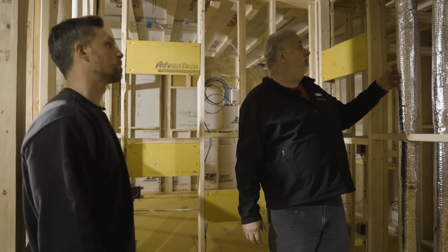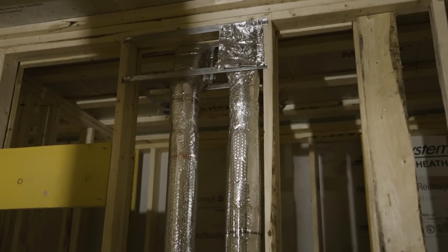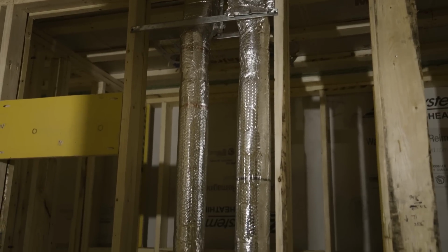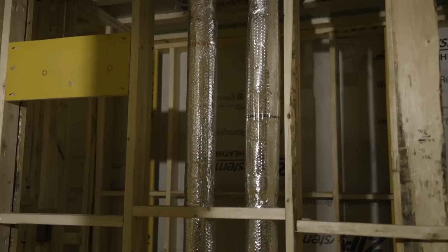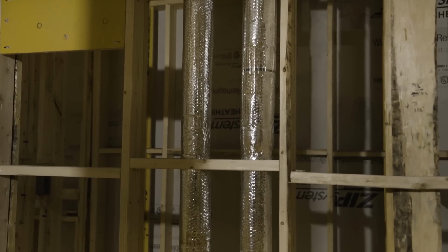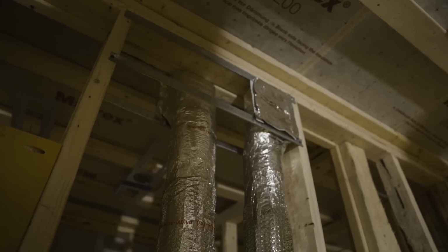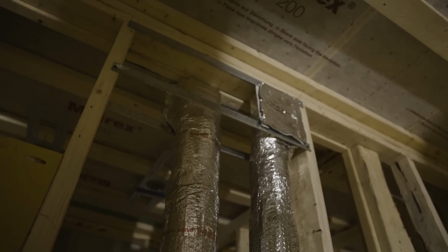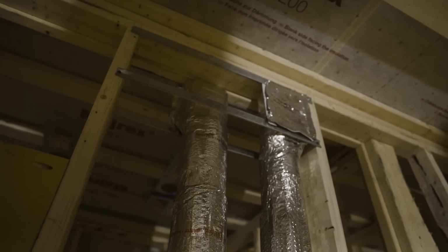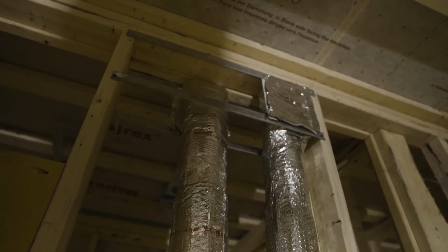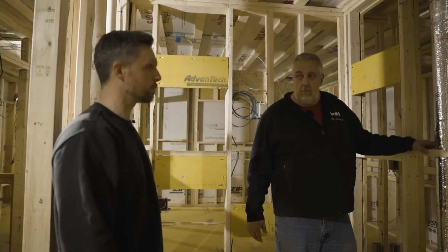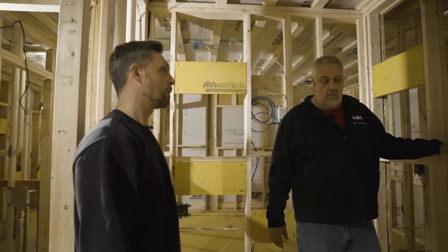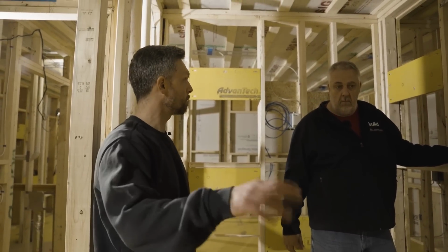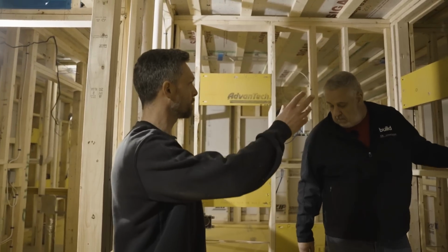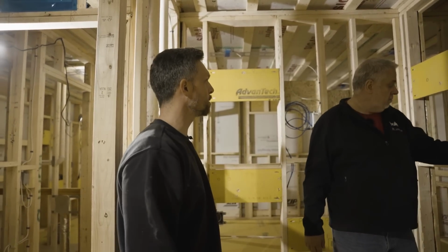I notice we have some ducts here, but these aren't heating or cooling ducts. Correct, these are for the ERV—we exhaust from the dirty rooms: bathroom, kitchen, laundry room in this instance. Just like the bathrooms, we'll mount a boost timer on the wall here, so if we're drying a load of laundry we can hit the boost timer and extract a larger volume of air while the machine is running.